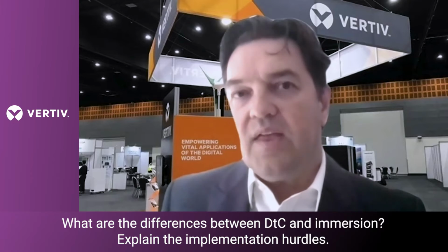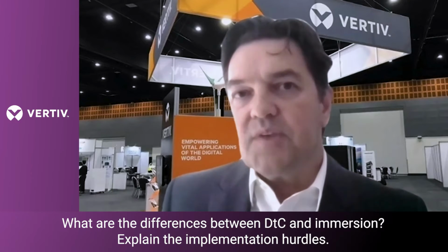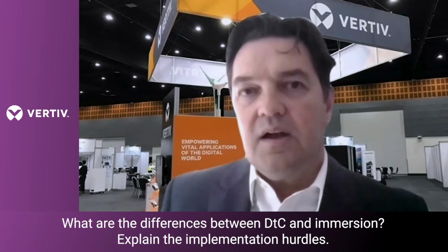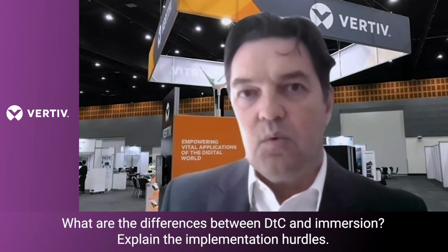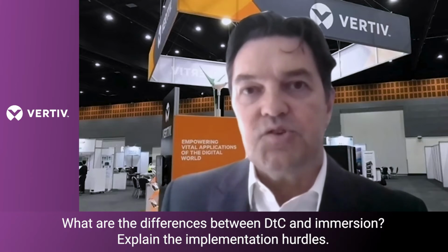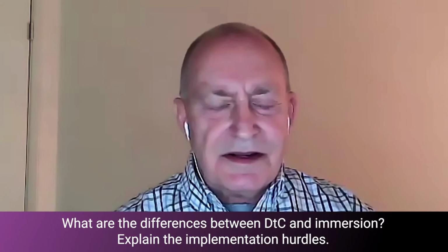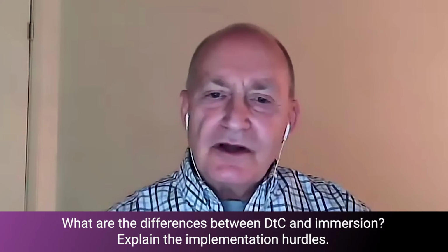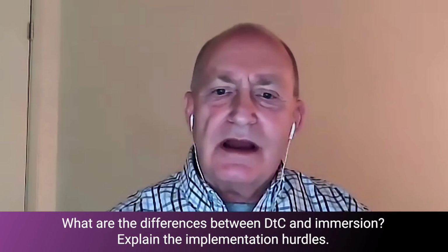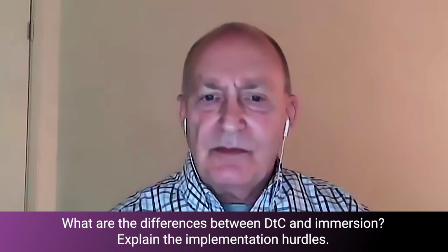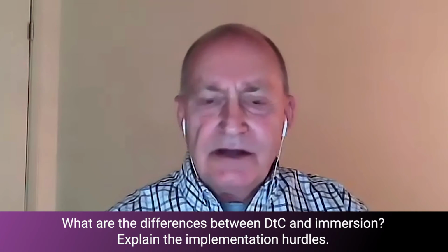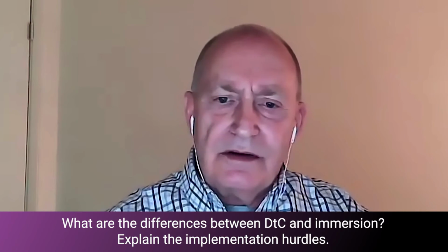So we're seeing where the rack density traditionally was 5 to 10 kilowatts for a traditional server. These are increasing to 30, 40, and in some instances planning for 60 kilowatts a server rack. Yeah, I was going to say at 60 kilowatts, air cooling is just not an option. So that was going to be my next question: what's driving adoption of liquid cooling? But I think you pretty much covered all that. It's a combination of applications and the advanced hardware required to do that.